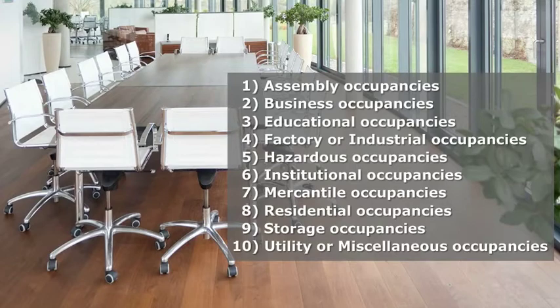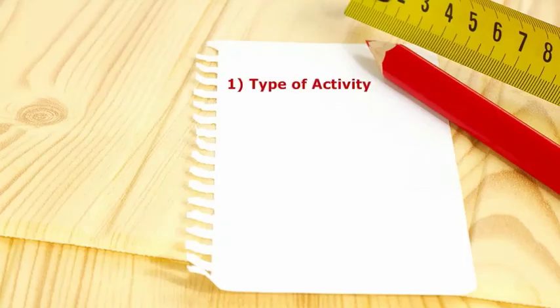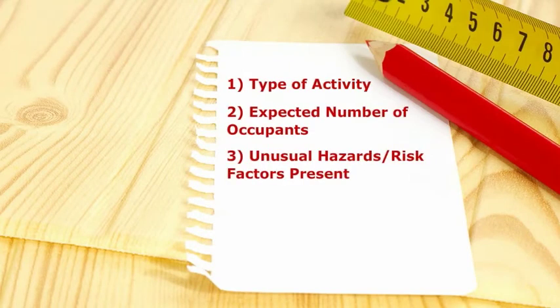Many of these classifications seem self-explanatory, especially if a building type is straightforward. But remember that three things must be known before the occupancy classification can be accurately determined: one, the type of activity occurring; two, the expected number of occupants; and three, whether any unusual hazards or risk factors are present.